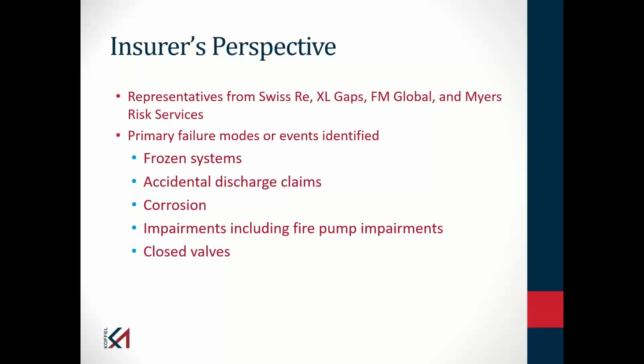And they also told us that primary failure modes of the sprinkler systems are frozen systems, accidental discharge claims, corrosion, impairments of the system. They kind of focused on fire pumps, but I'm going to refer to impairments generally because that also kicks in closed valves. Two-thirds of the fire incidents where a sprinkler system fails to control the fire, the reason the system did not control the fire is the valve was closed or mostly closed. And I don't really have time to go into, well, I'll tell you one story, but there's multiple cases that I could identify where we had a loss that was other than what was normally expected.